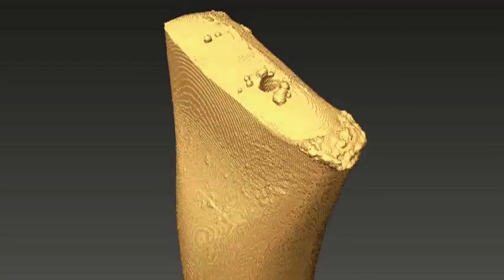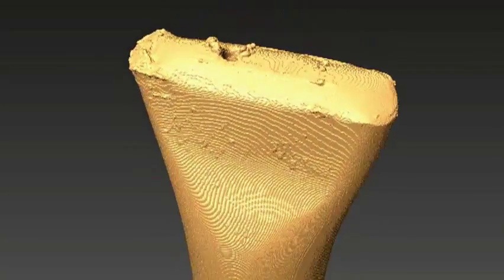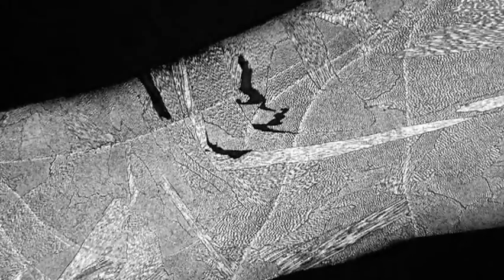The materials that we selected at the time that we made the vessels had nothing to do with laser welding. In fact, laser welding wasn't even conceptualized at the time. Back then, they used a small tube to insert tracer gas and to backfill gas into the containers themselves. The tubes are crimped and sealed, and so we were able to successfully drill through the tubes, but when welded, we saw cracks in the welds. We had our material scientists take a look at it.